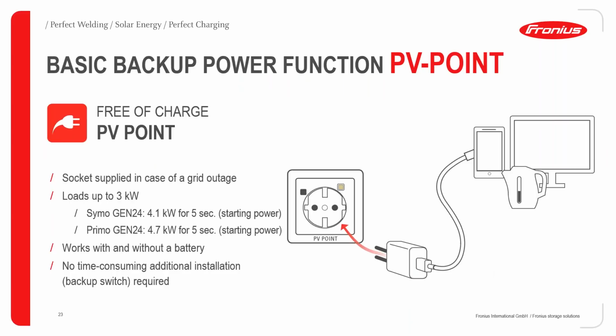Basically the PV Point is a socket in a household, you can see it here, like in the picture. It's its own exit on the inverter, on the AC side you have a one-phase exit, which you can install as this socket, and then supply loads up to 3 kilowatts. That means this PV Point is then only operating in case of a grid outage.